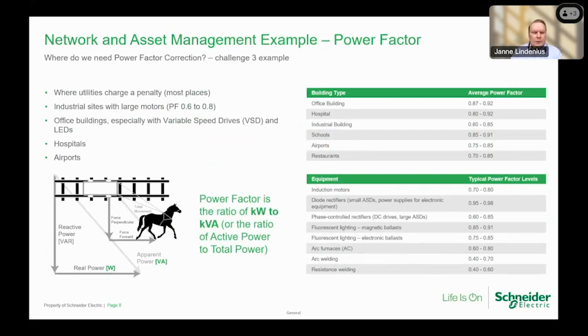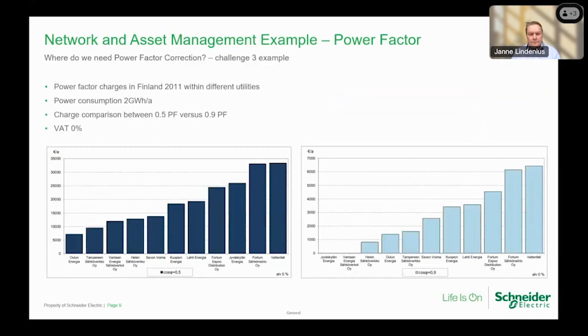So where do we need power factor correction? Challenge number 3 example. The most common case is when your utility charges for reactive power. The amount of reactive power taken or given and the charge depends on the utility. As you can see from the charts, the power factor varies between facility types and device types. Facility range starts from 0.7 and device range starts from 0.4. The target for power factor in most utilities is above the 0.9 level. Next slide, please.